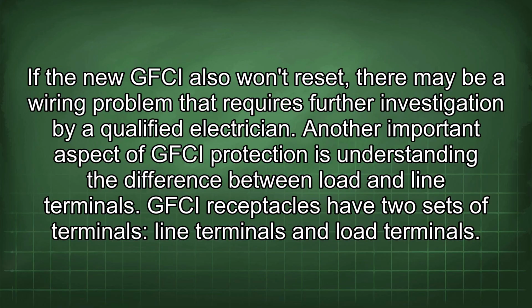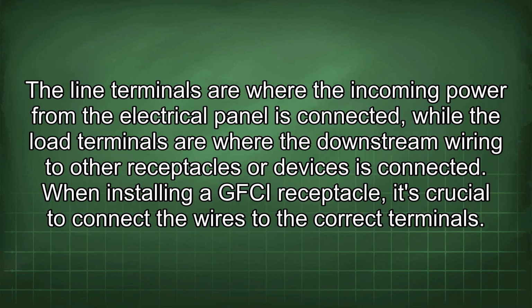Another important aspect of GFCI protection is understanding the difference between load and line terminals. GFCI receptacles have two sets of terminals, line terminals and load terminals. The line terminals are where the incoming power from the electrical panel is connected, while the load terminals are where the downstream wiring to other receptacles or devices is connected. When installing a GFCI receptacle, it's crucial to connect the wires to the correct terminals.